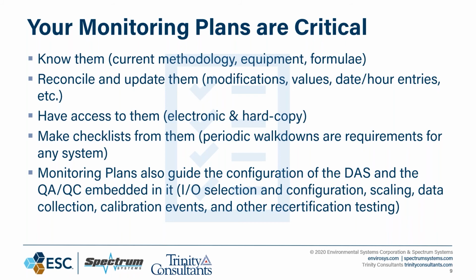Your monitoring plans guide the configuration of your data acquisition system and the QA/QC that ultimately becomes embedded in it, and that is what tags you're monitoring, how it's configured, how it's scaled, what precision do you have to report these parameters at, how often the data is collected, how often you calibrate the system, any other recertification testing. All of this is guided by your monitoring plan.